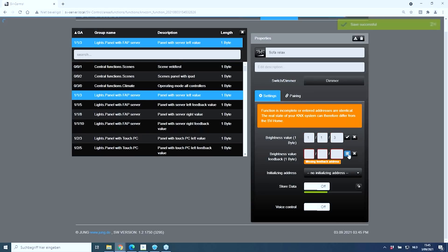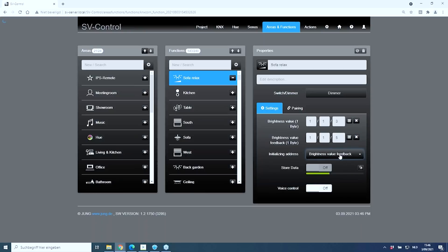I can enter group addresses manually if I know them, or select them from my list — for instance, this one as the send address, and of course a feedback address as well to get the status of the light. When the Smart Visu Server starts up, you can define a read address where it retrieves the actual current value — in this case, the brightness value feedback — meaning it will perform a read at that address to obtain the actual status.